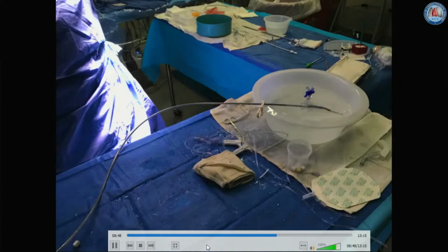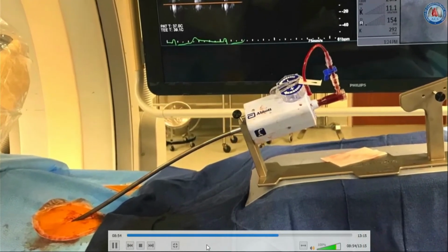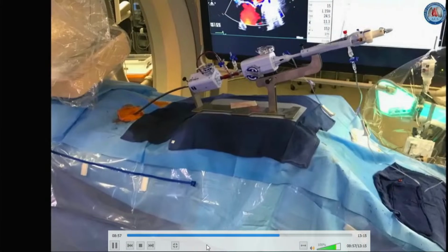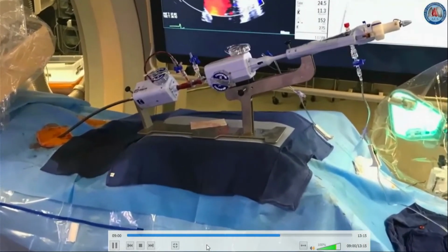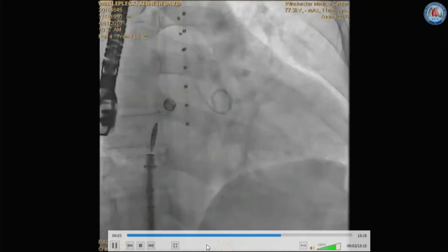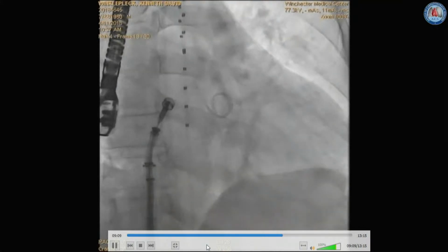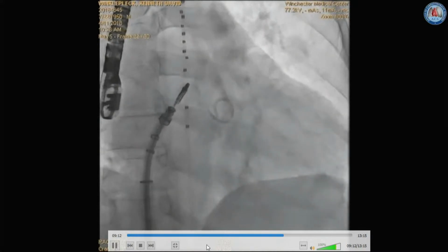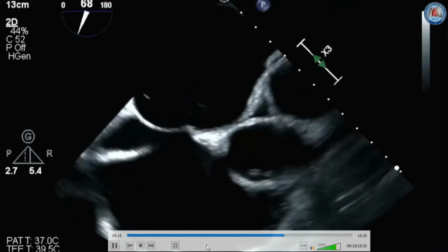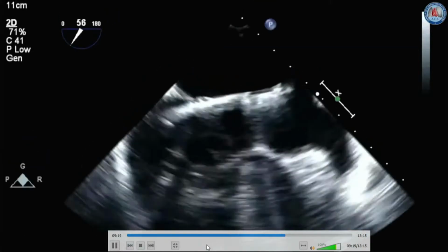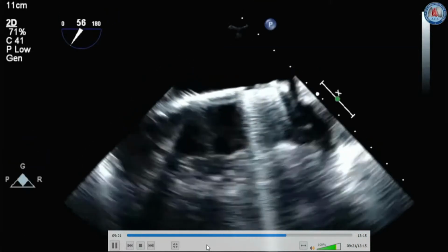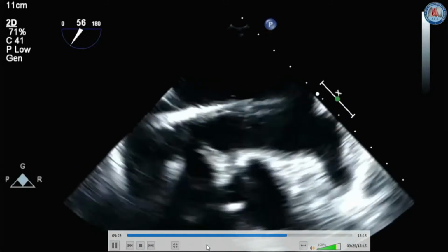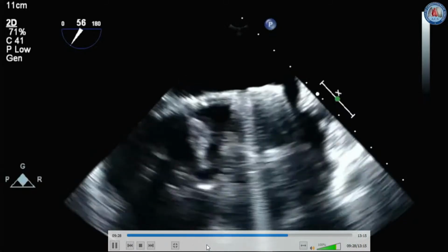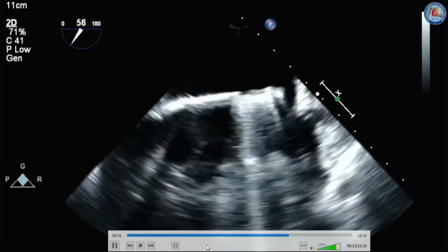Steering and positioning of the MitraClip device, requiring position of the metal stabilizer over the right leg and preparation of the clip on the back table with removal of any air within the system. And the clip delivery system is then advanced carefully into the left atrium until the system tip ring marker is centered between the sleeve alignment markers with a fluoroscopic confirmation, which is often referred to as straddling. Once this is achieved, the delivery guide and the delivery system are then maneuvered within the left atrium carefully using TEE guidance to clear the left atrial wall, the Coumadin ridge, and position the MitraClip centrally over the valve.